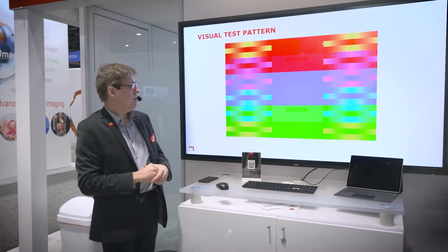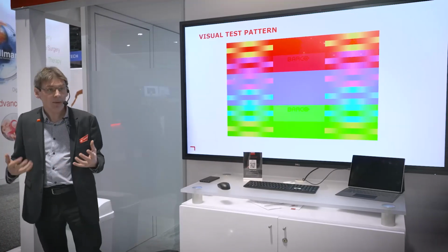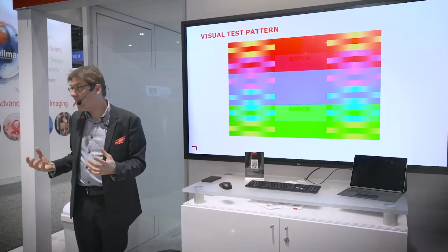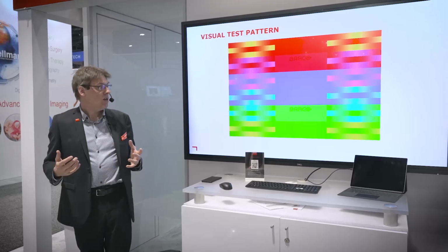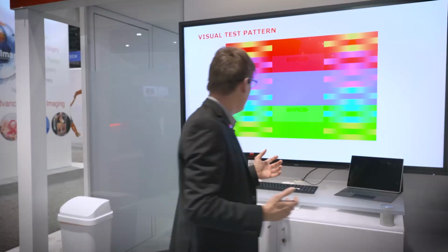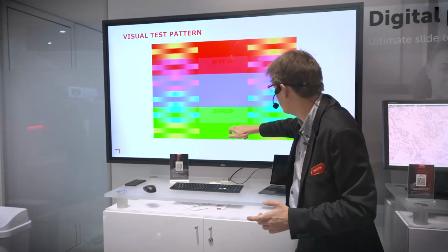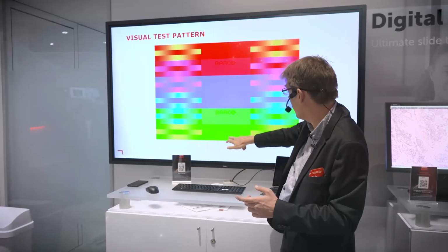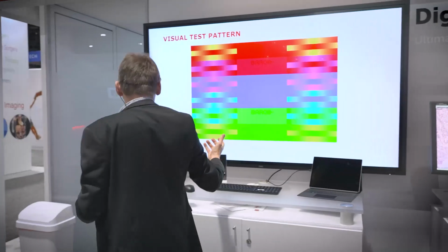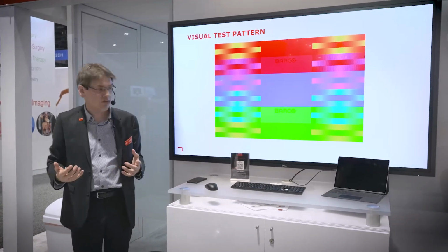Actually, this is really nice. So we also created a test pattern, which Barco also included in its QA Web quality assurance software. If your display is properly calibrated to CSDF, then you should be able to see all the targets in this pattern. Here you hardly see any. So from where I am, you can see a Barco logo in the red. I don't see anything in the blue, and if I really look in detail, I see a little bit in the green as well. So it's a very easy way to quickly, in a visual way, see is it properly calibrated or not.